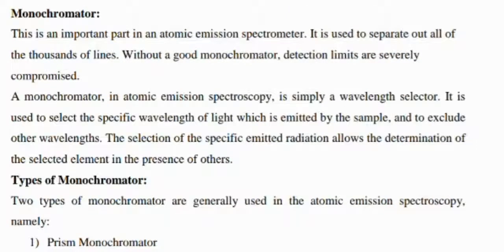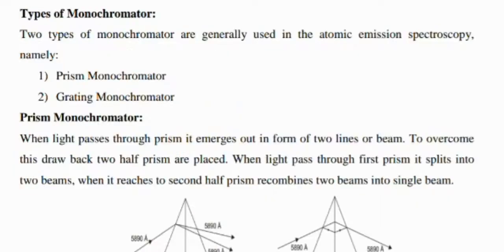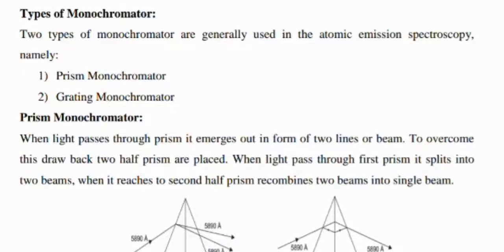Monochromator, like in atomic absorption, is also an important part and is used to separate out all the thousands of lines. It has two types: prisms and grating monochromator. When light passes through a prism, it emerges in the form of a line or beam. Grating monochromator gives better results and replaced prisms with linear dispersion.